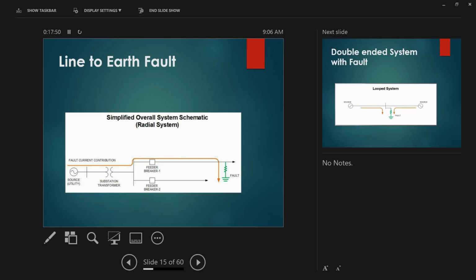line to earth fault. So of course, the source. You have the source here, the substation, and feeder 1. If you have a fault here, this feeder should not be affected, because the current will return through the neutral. So it's some kind of loop. That's why if your earth is not really good, you will not reach the specific setting of the fault, and sometimes your relay will not pick up the expected trip that you want.